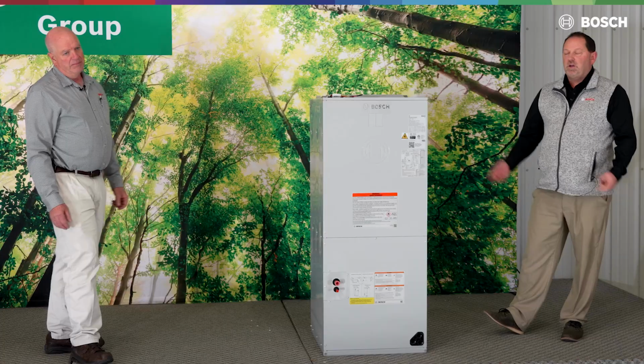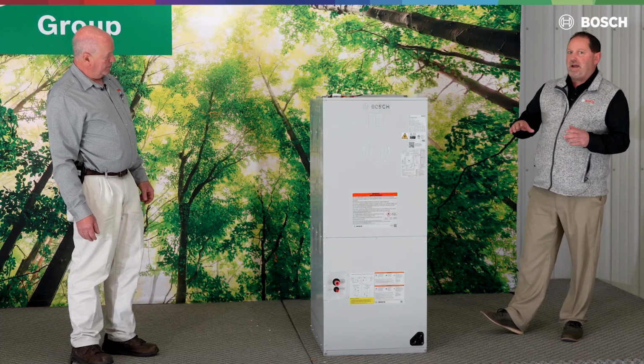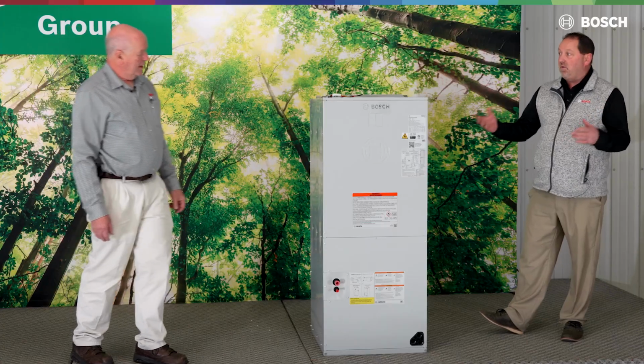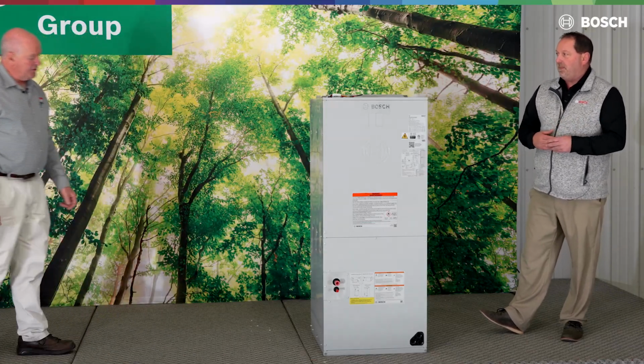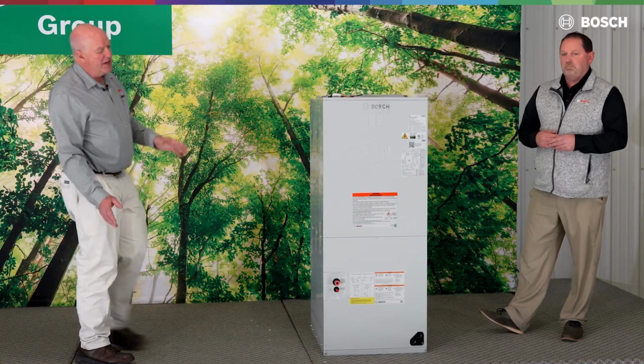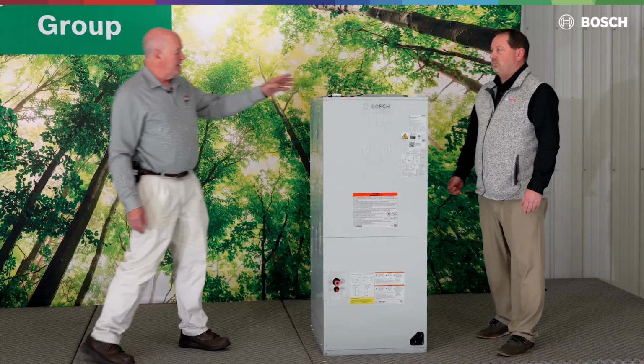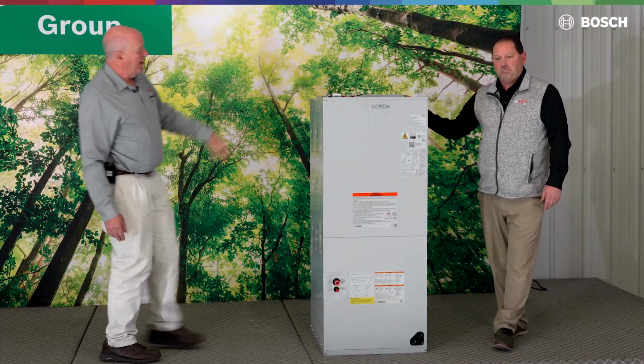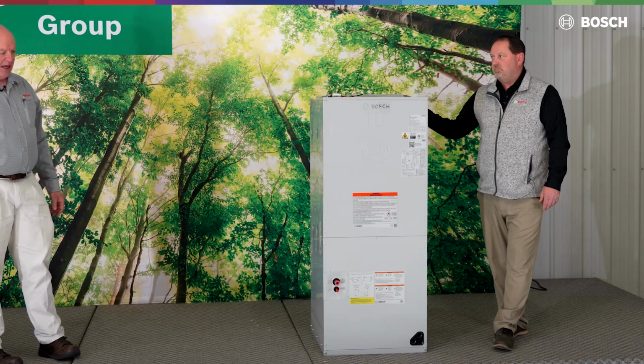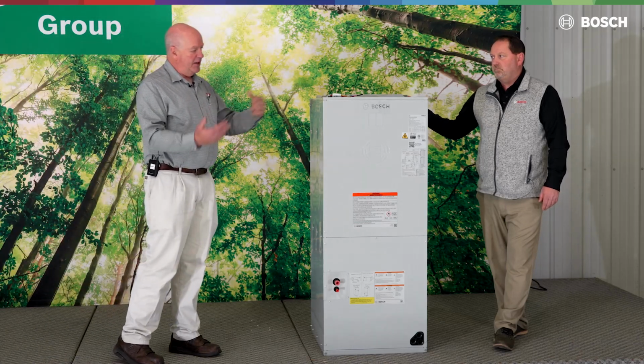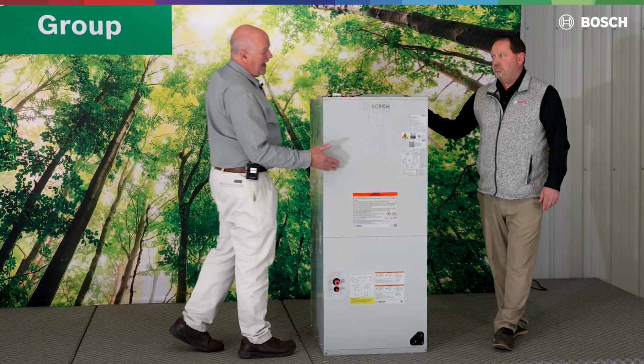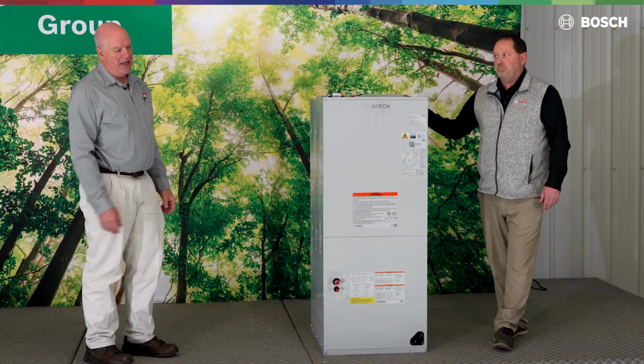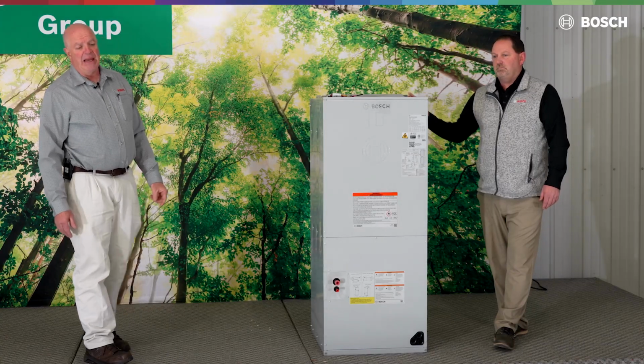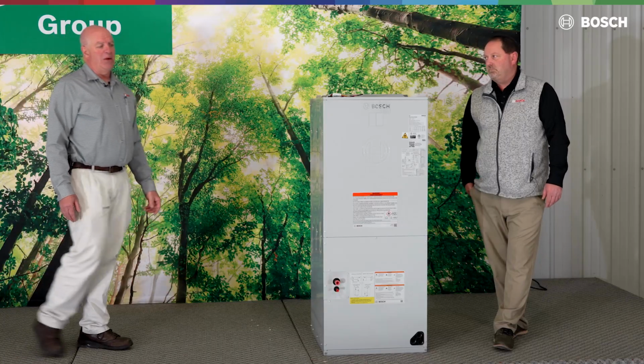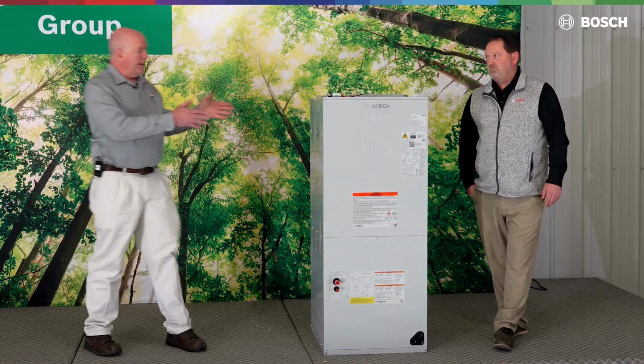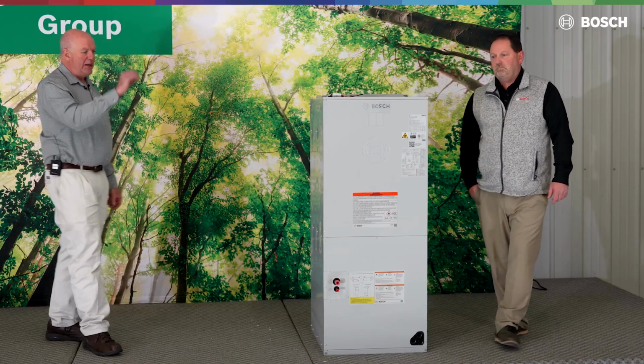this unit. Okay. You know, earlier you mentioned communication. It's my understanding that this has multiple ways of communicating, whether it's our thermostat or somebody else's thermostat. Please talk about that for a second. It does. So we have what we call our A version, which is kind of the easy way to go with someone else's product, in which we have the T1, T2 sensor involved. We still have a communication 2-wire that goes between the air handler and our outdoor section at that point. They're constantly looking at the temperatures and adjusting the fan speed based off of what's happening and the coil temperature and dehumidification based off the humidity set point of the thermostat and what the actual home is at that point. Option B is using the Bosch Cloud Bosch thermostat, the BCC 110. And with that application, we look at the actual temperature at the thermostat for what is the set point and what is the actual temperature.